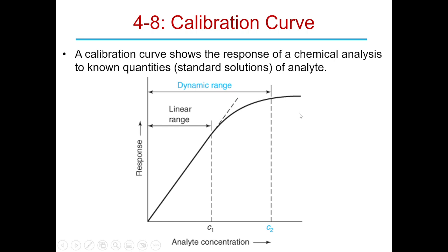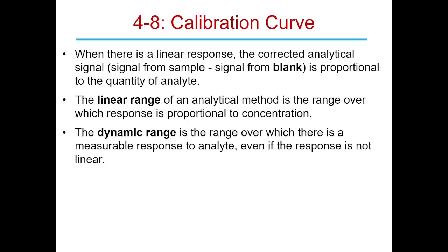It was exceeding our dynamic range for the instrument. So literally everything was just background. We couldn't see past the background because the background was just so bad. Okay? And that's just because of the signal from the air. Well, air that was vacuumed to a fraction of the atmosphere, but still was too much.